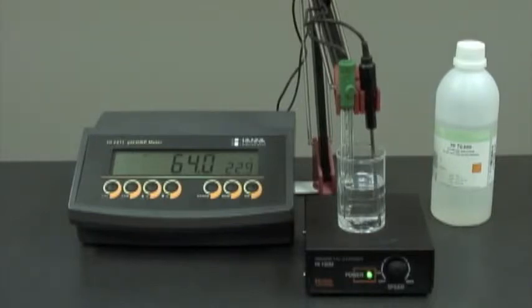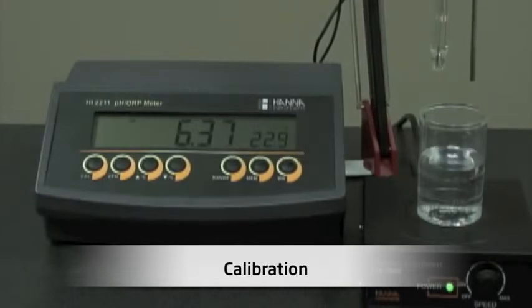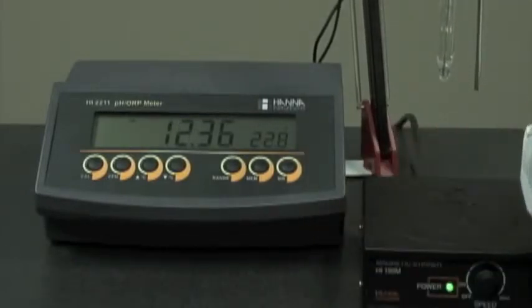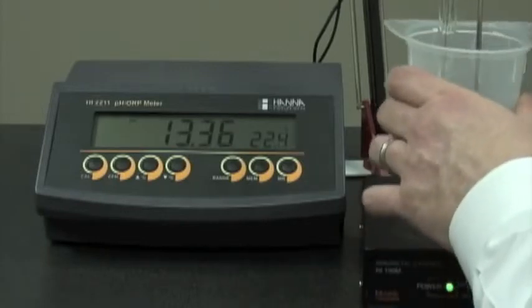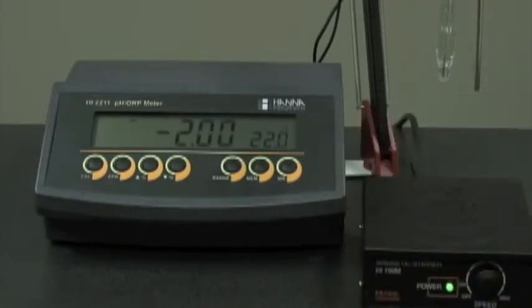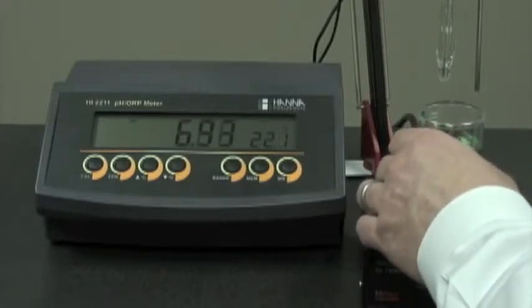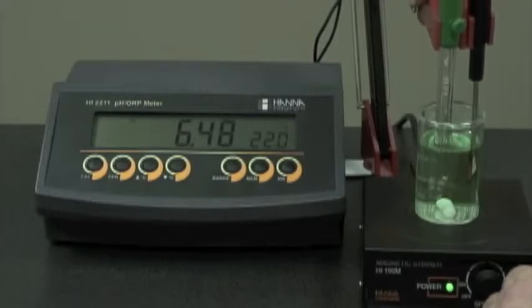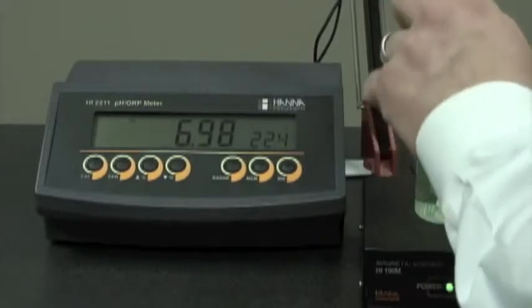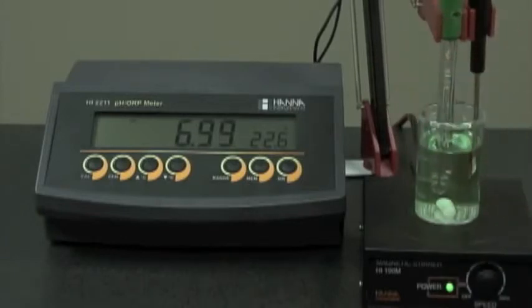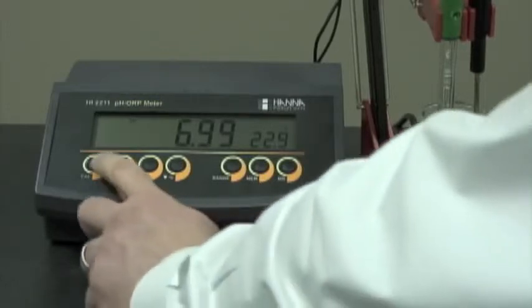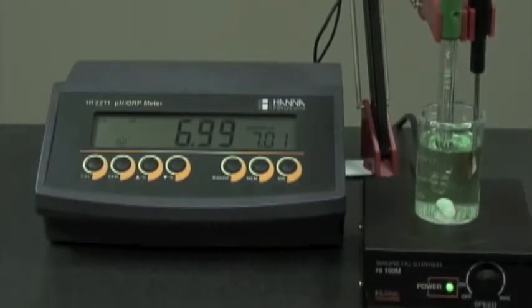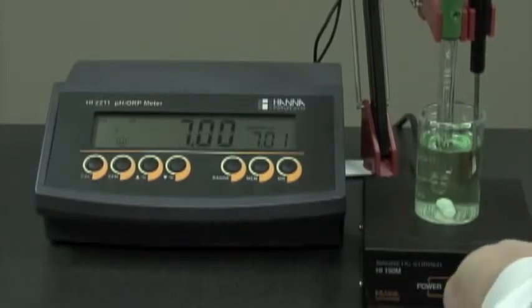Now we're ready to calibrate. We remove our probes from the storage solution. We rinse them off with deionized water and place them in pH 7 buffer. We remove the refill cap. This creates positive head pressure and allows the electrolyte to flow through the junction, creating a faster response time. We hit the cal button and we turn on the magnetic stirrer.